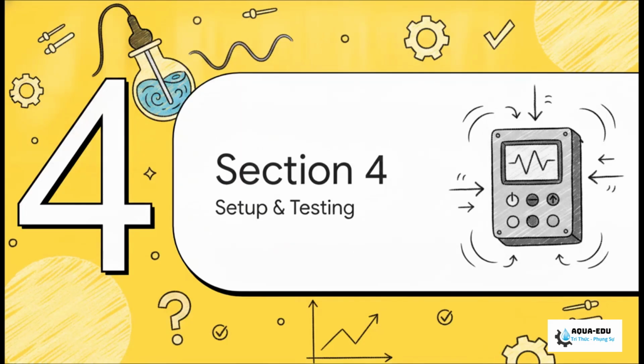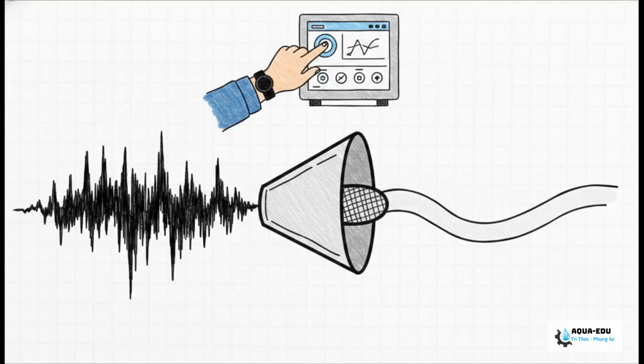Next up, Section 4, Parameter Setup and Testing. On the touchscreen interface, make sure Automatic Temperature Compensation, or ATC, is turned on, utilizing the built-in Pt100 or Pt1000 sensor. Set your measurement range properly, which is usually 0 to 14 pH, but I want to give you a great pro tip here. I highly recommend you set the damping factor between 2 and 5 seconds. This is the Goldilocks zone.